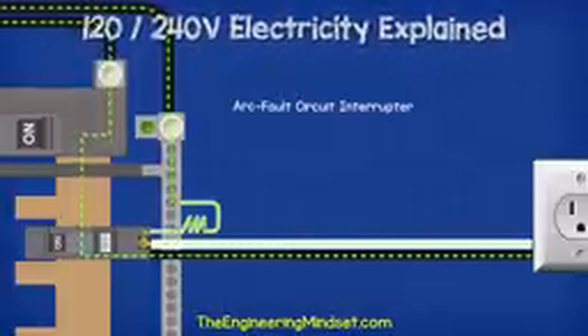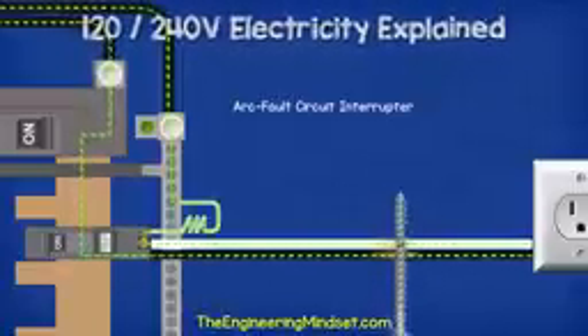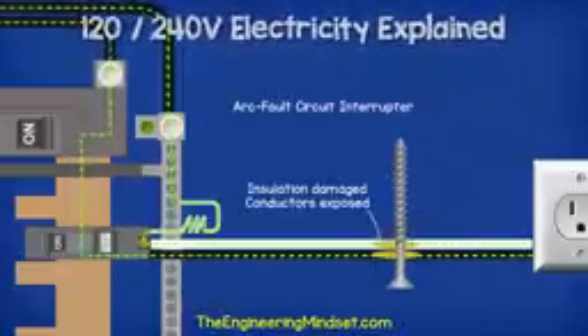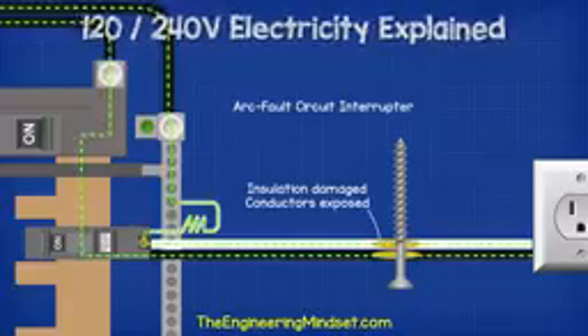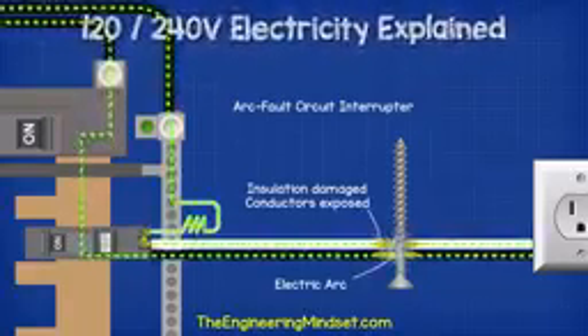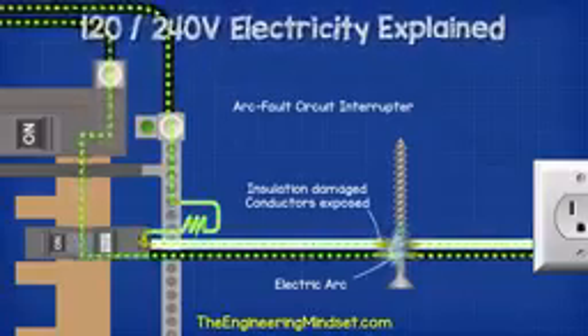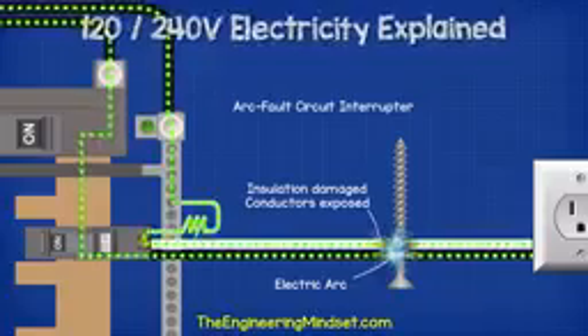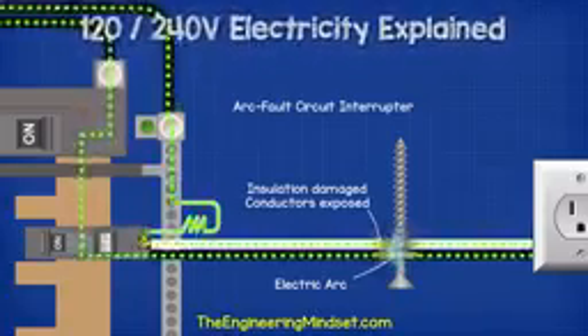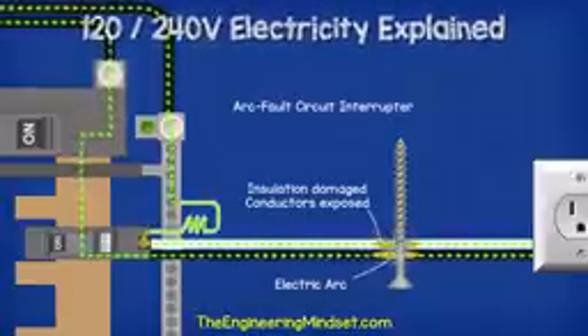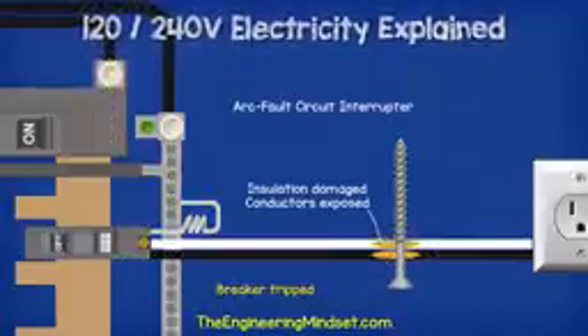But if, for example, a screw was accidentally inserted very close to the cable and removed the insulation to expose the copper wires, the electricity could now potentially jump across or arc from the hot wire and into the neutral. The arc is incredibly hot and causes most residential electrical fires. As the arc occurs, it creates a unique signal in the electrical cable. The circuit breaker can detect this and will automatically trip to cut the power.